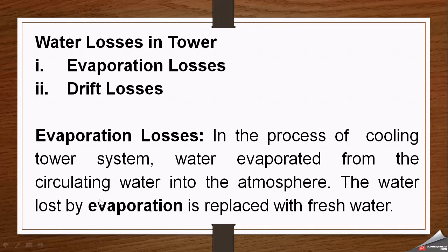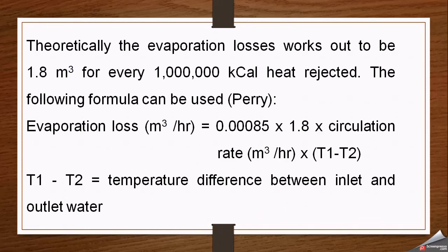The water lost by evaporation is replaced with fresh water, since losses go out to the atmosphere and must be made up with fresh water. Theoretically, evaporation losses work out to be 1.8 cubic meters for every 1 million kilocalories of heat rejected. The formula normally used to calculate evaporation losses is applied where T1 and T2 represent the temperature difference between the inlet and outlet water of the tower.